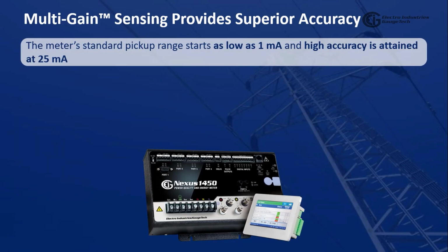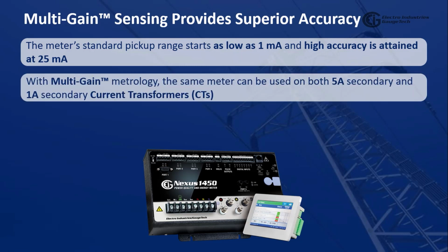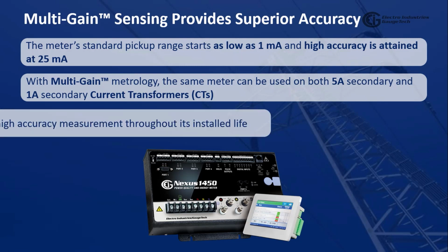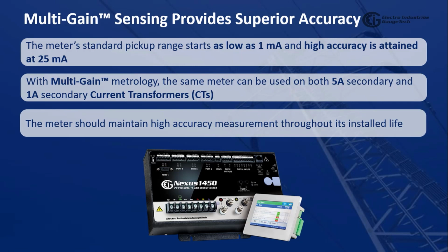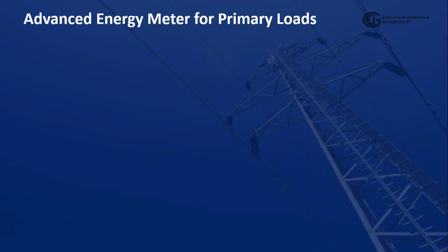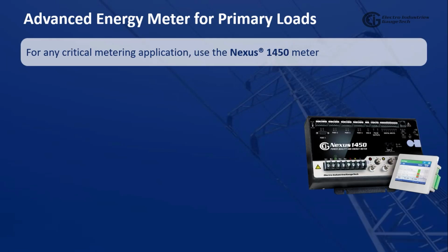The meter's standard pickup range starts as low as 1 mA and high accuracy is attained at 25 mA. With multi-gain metrology, the same meter can be used on both 5 A secondary and 1 A secondary current transformers. The meter should maintain high accuracy measurement throughout its installed life. The Nexus 1450 is an advanced energy meter that supports primary metering load requirements. For any critical metering application, use the Nexus 1450 meter.